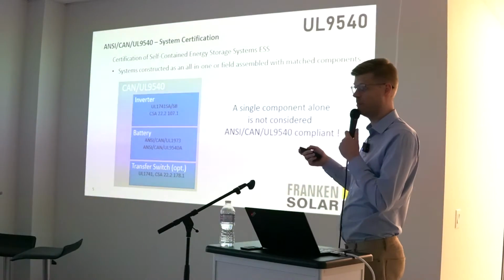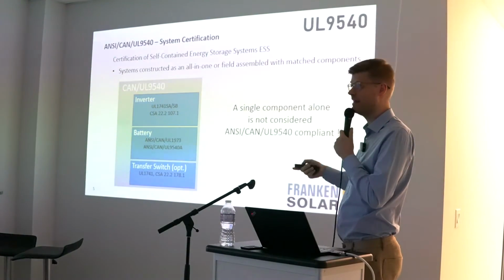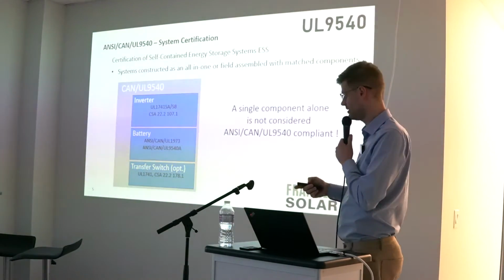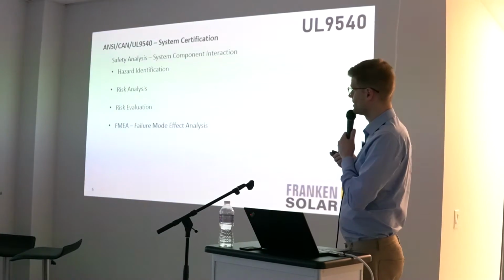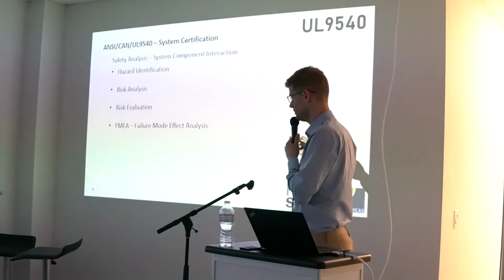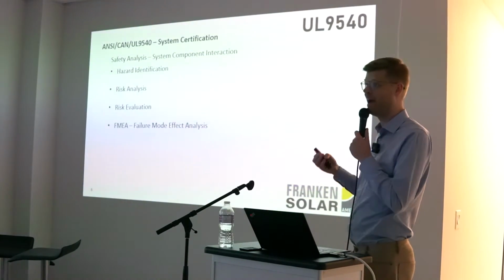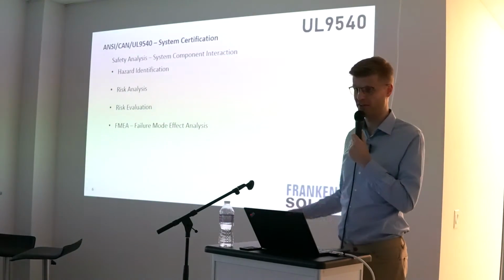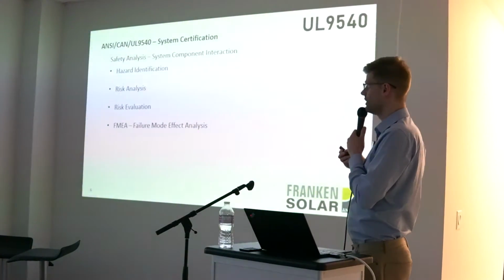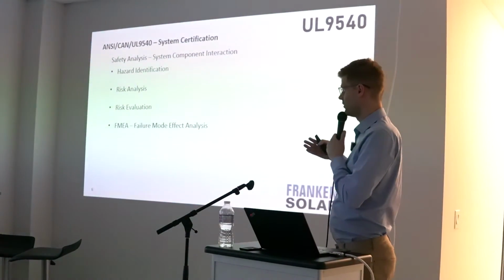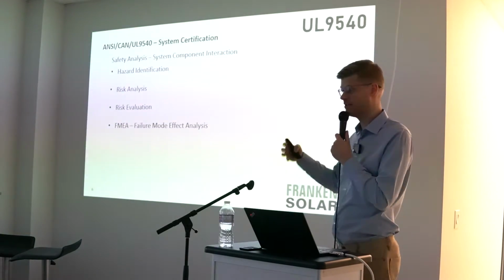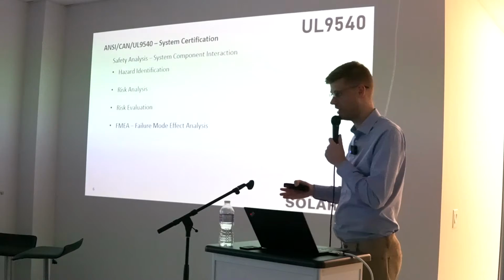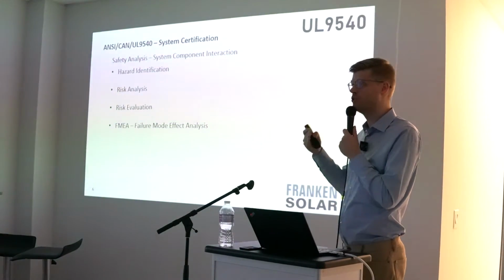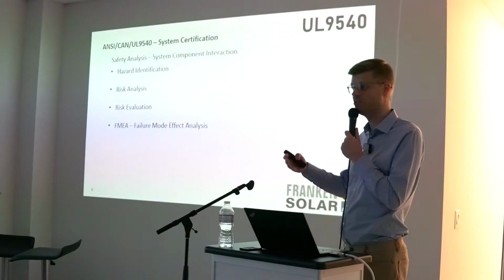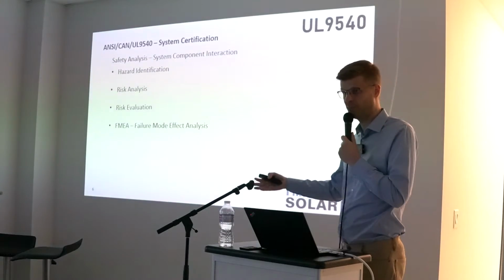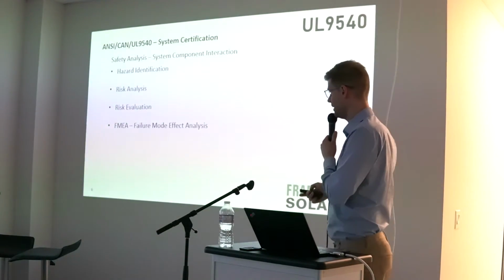So every system that has a combination of an inverter and another battery is a different certification and will have different documentation to it. The main focus of that system certification that was introduced to the Canadian and the US standard is to identify hazards specifically in your residential dwelling. No one wants to have a fire in their home or their basement. So risk analysis and risk evaluation, together with a failure mode analysis, where engineers and the technical team with UL or CSA or whichever agency is doing the testing think about what could go wrong, what different failure modes could lead to a problem in that system that could be a catastrophic problem to the customer, their home, and maybe their well-being.